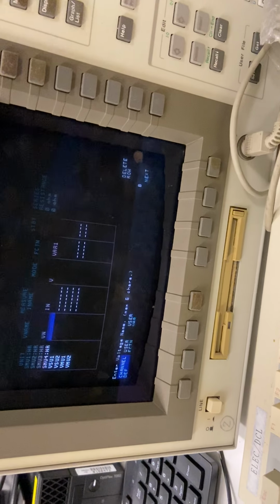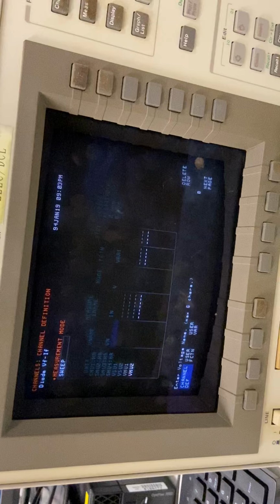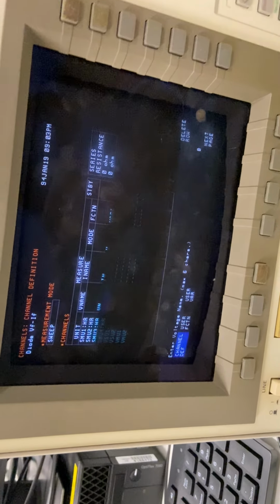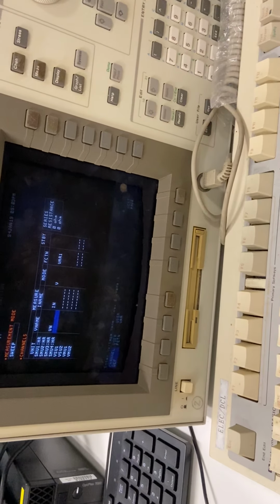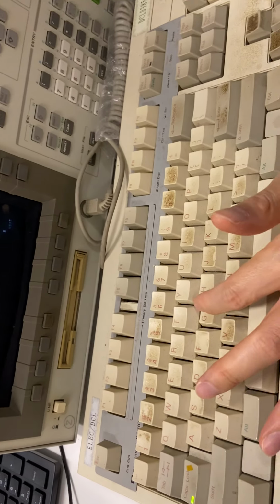One of the terminals is already set as SMU3, and the other is SMU4. That's connected to the back side of the wafer, the chuck, and that is the ground actually. Since you already know it's the ground, we can simply name it V ground.